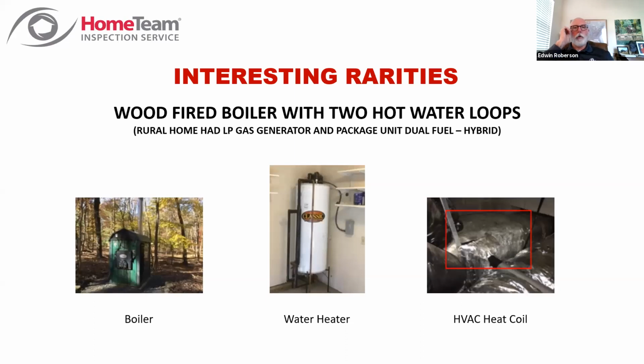So let me share with you a few interesting things that I've seen. This house, and it was actually, if you recall a few slides ago where I showed the outdoor package unit that had the gas furnace integrated in with the heat pump, this was the same house. In this one house, we had a wood-fired boiler outside, and you had loops to where you could run auxiliary hot water and an auxiliary HVAC heat coil, water heat coil in that house.